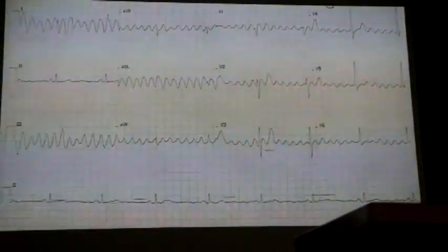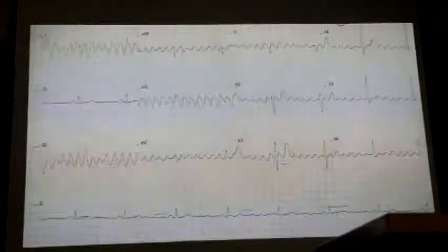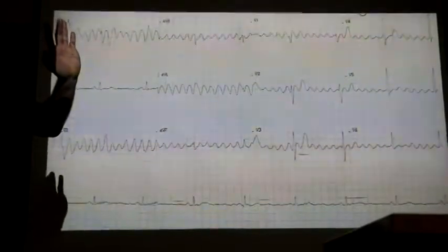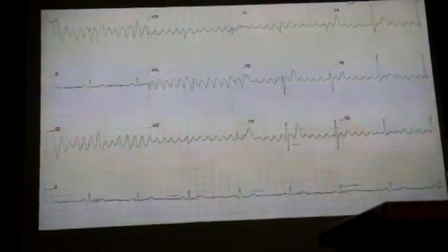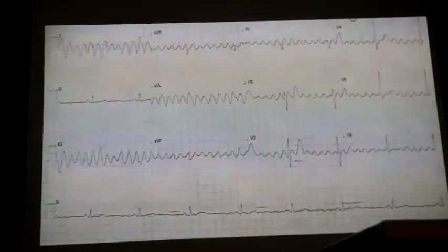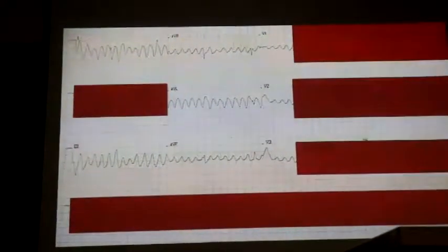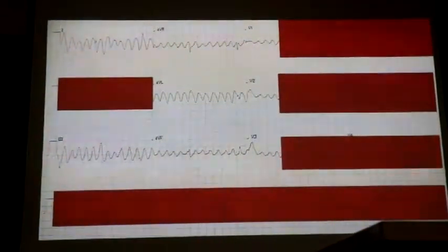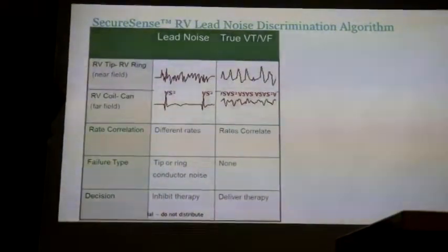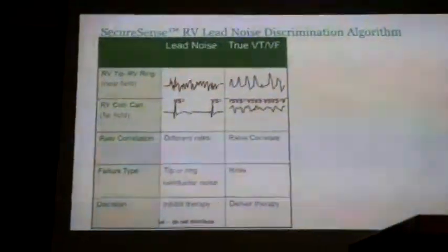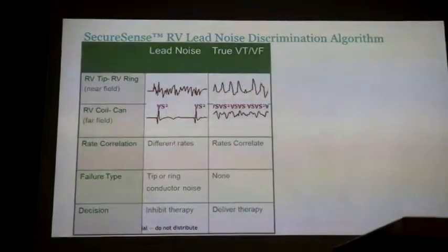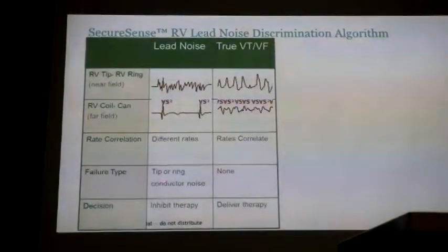So this is kind of what SecureSense is doing, right? You know the SecureSense algorithm. It's saying, okay, it really looks fast on one electrode. Check another electrode. They go, that's normal. Don't shock the patient. Hold off, okay? That's pretty much what it's doing. But this would be the reverse. You will find the higher rate on the can to coil, but in the tip to ring, it will be normal. Sure, yeah. So this is SecureSense. Let's say this is the near field, and it's going very fast, and then you check the far field. So that's generically what it does. If it's fast on near field and slow on far field, the rates do not correlate. So the device says this is some kind of noise.